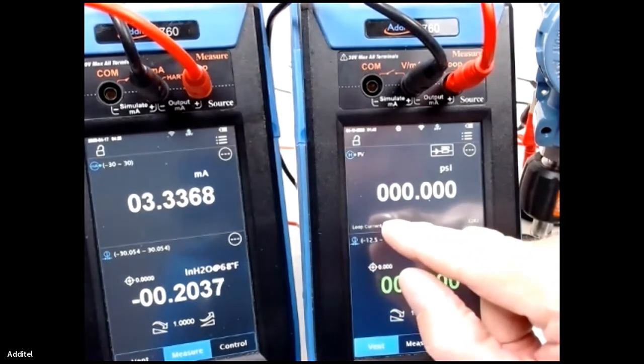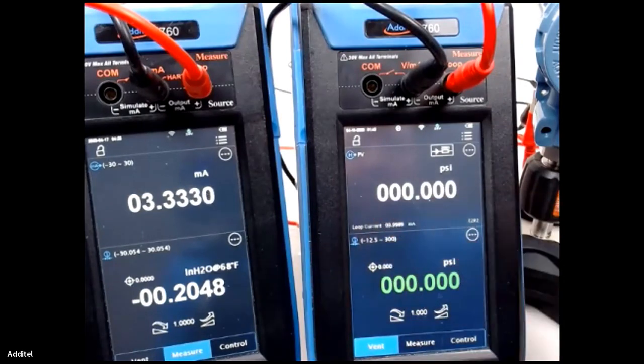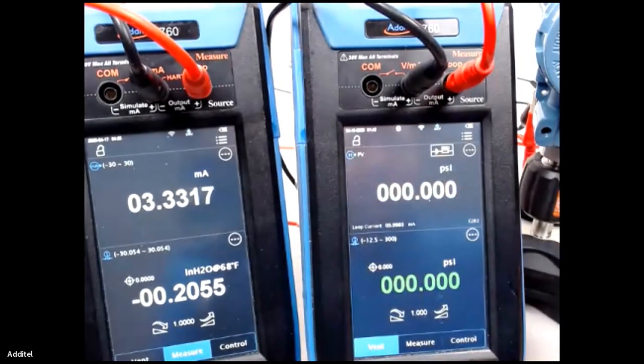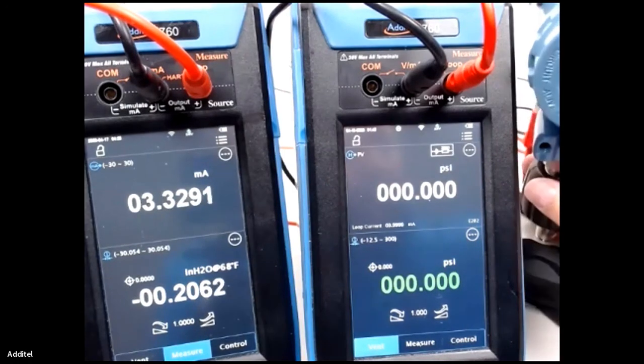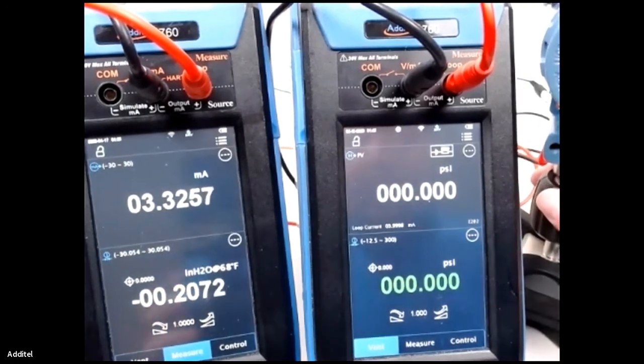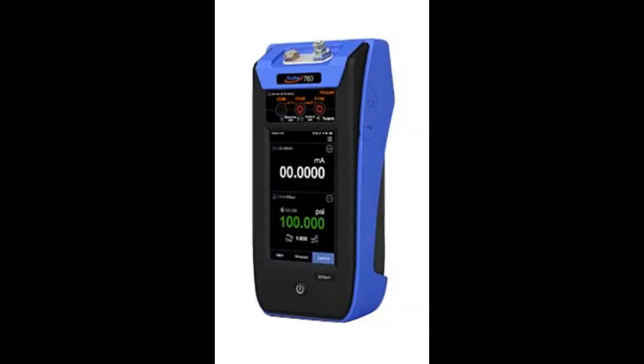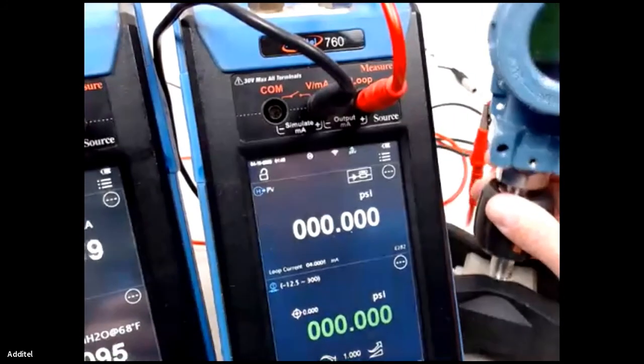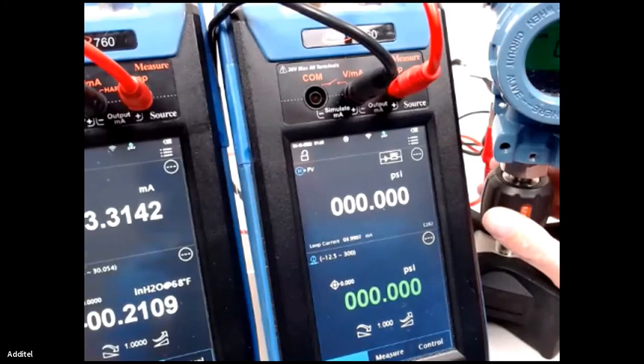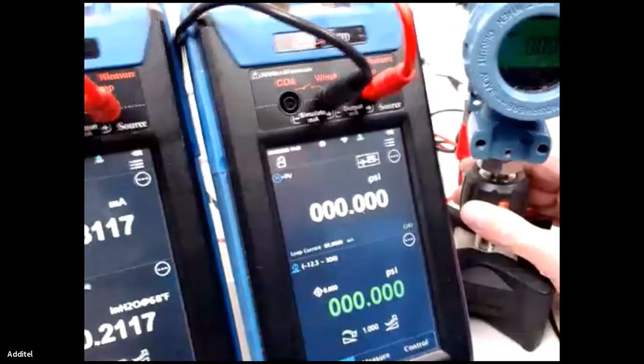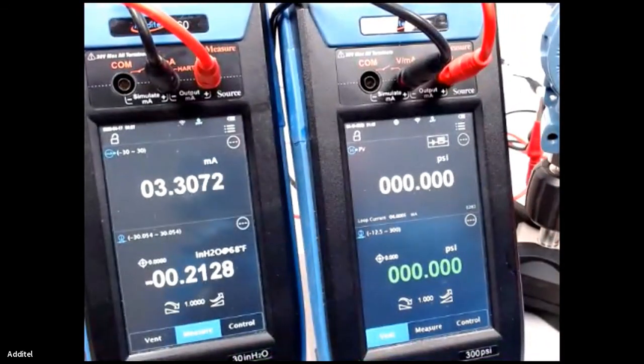I don't know if you guys can see this HART transmitter. If I can turn the camera the right way, it's backwards to me. That's the HART transmitter, and I've got that powered up with the 760. So you can provide the power you need to power your transmitter, or you could turn that off and power it the other way. I'm going to go back here to the units where I think you can probably see it a little better. But that's the unit we're actually going to do the calibration on.